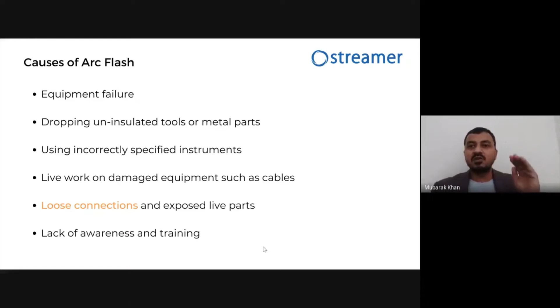These loose connections can come anytime. There is one more cause of arc flash that is not mentioned here: in a vacuum circuit breaker, the vacuum bottle fails and causes a flash. That is also one of the causes. But anyway, these are the operational parts. You cannot do anything; you just need to maintain. But loose connection is the place where this normally happens and we are not able to avoid it. So this is a condition monitoring issue. All others are best practices or good equipment issues, but loose connection is a condition monitoring issue.